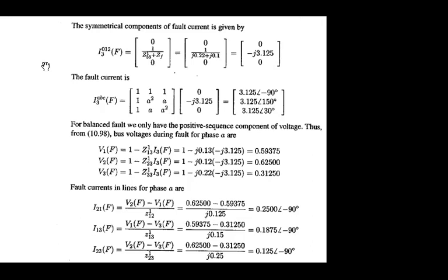So that we can handle a lot of buses together, a large number of buses. Large bus calculations will be easier or simpler, because by the inspection method it will be difficult for you. Likewise, for short circuit or fault current calculation, if you apply the Thevenin concept, you can do that, but it has some limitation. That means up to a certain limit you can do it by the Thevenin concept or equivalent circuit. But when you move to a large circuit, it will be easier to shift the idea to the bus building concept, Z bus. From Z bus you can find the fault current. It will be more convenient.